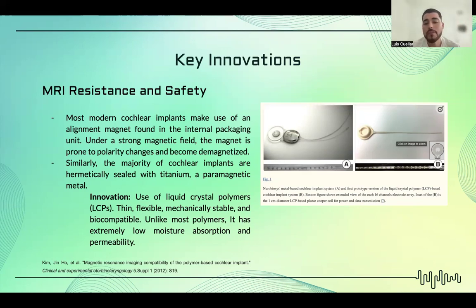So what a lot of people are doing nowadays with the commercial cochlear implants is making it easy for the magnet to be surgically removed. That has been the approach that has been taken up as of late. I couldn't really find much of an innovative solution to this issue. However, I was able to find a solution to the titanium package issue. Even though the magnet can be surgically removed, you're still left with metallic components inside of the internal unit. You cannot remove the whole internal unit. That internal unit is made up of a titanium package.